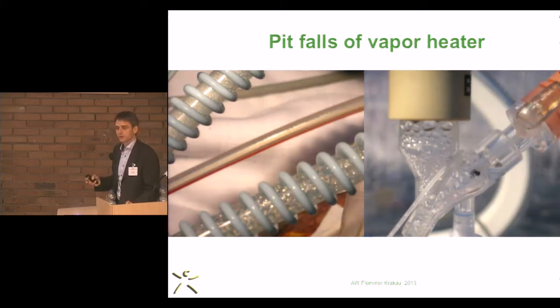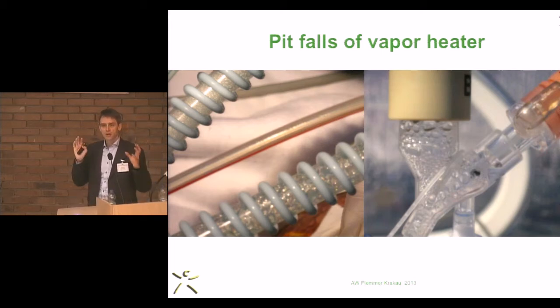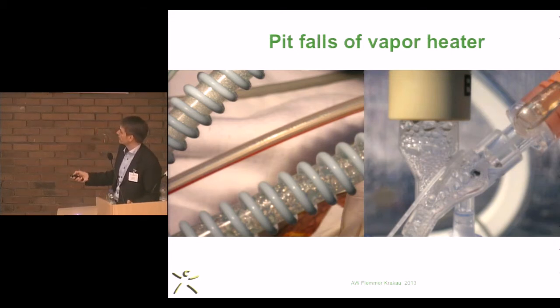How does rainout occur? This now is a ventilator tubing that has heating wires on the outside of this tubing. However, as you can see, here's the inspiratory limb, here's the expiratory limb, that in the inspiratory limb you have a very small droplet rainout, indicating that the environmental temperature might be quite too low, or the settings of your tubing heating is too low, and result in rainout and loss of humidity in your ventilator tubings. And the same is true at the Y-piece. This is a closed suctioning device. You might notice a lot of rainout here.